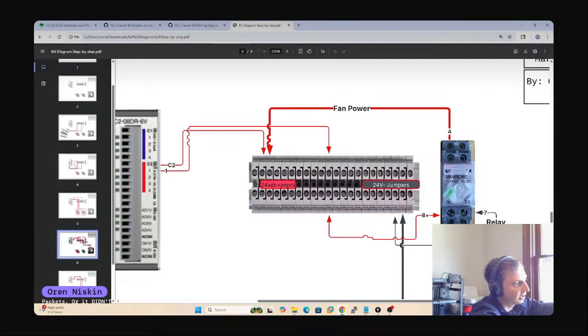So when you send current through these things, it'll let power flow through for whatever that is, like our fan. But if you think about this, this could be an enormous ship thruster, or it could be the compressor for your air conditioning, or it could be anything where you want little power to turn on big power. This could be 5,000 volts, this could be 24 volts. So it's kind of incredible that 24 volts DC can turn on 5,000 volt loads through a relay.